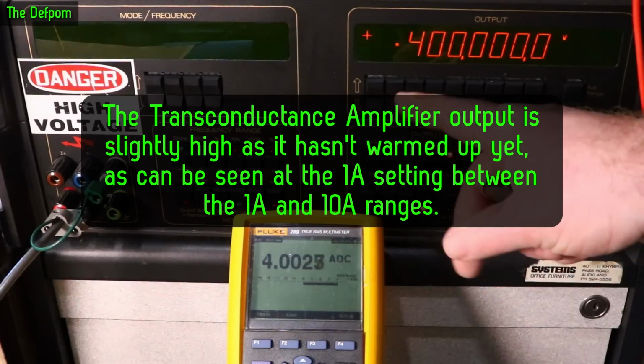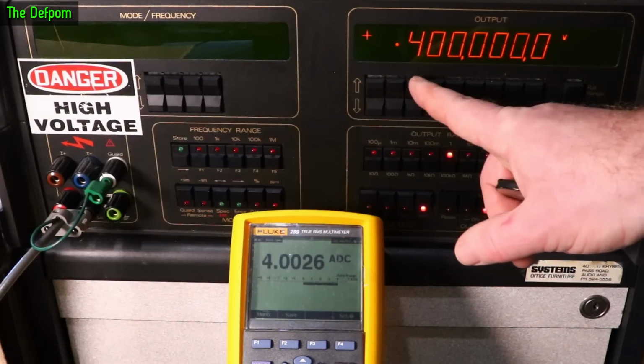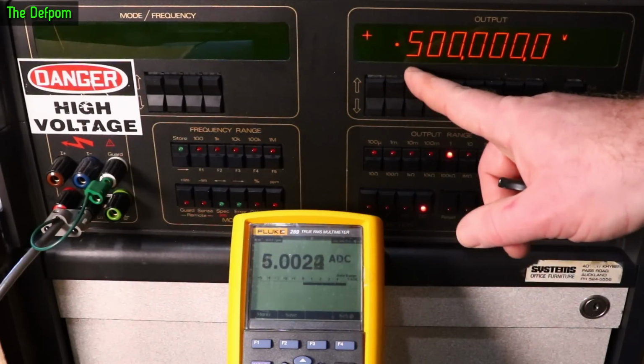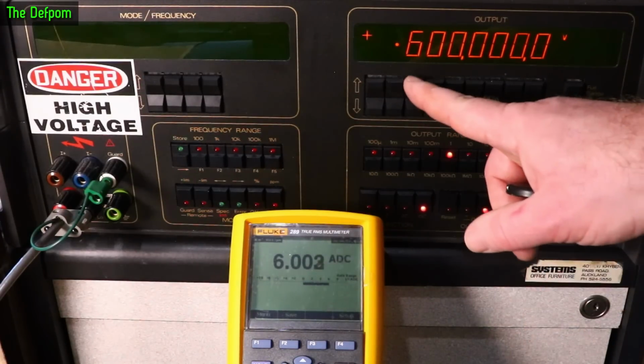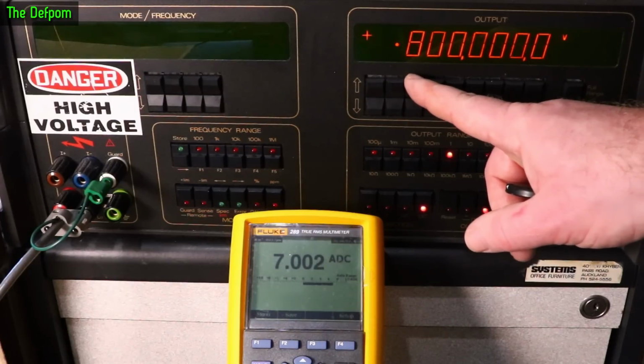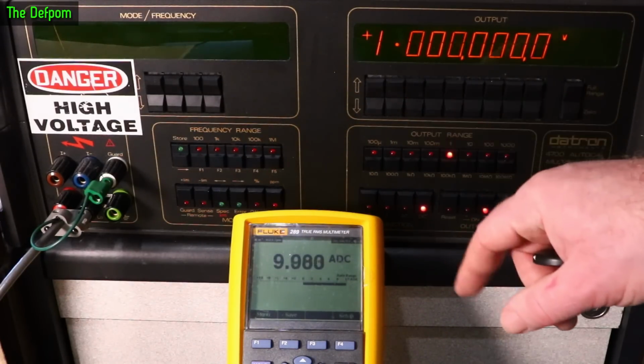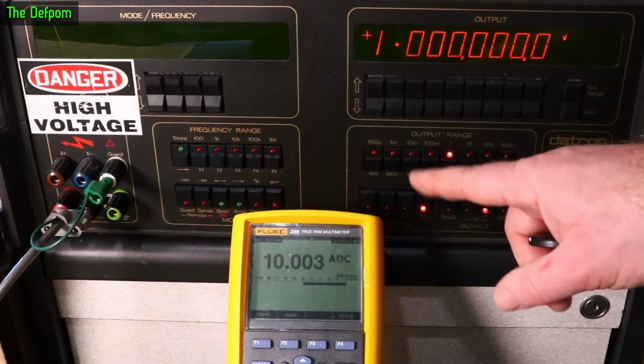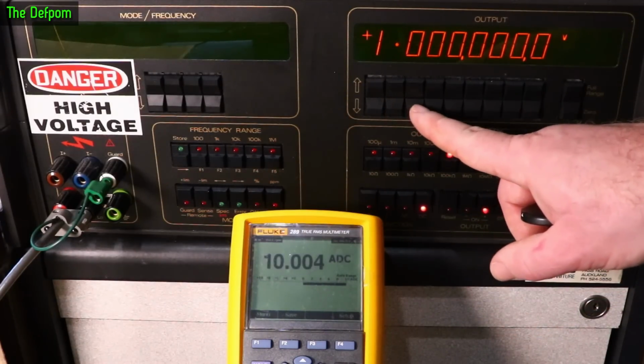Now my transconductance amplifier is not warmed up yet. It should warm up for about an hour or so really, and I've only had it on for a few minutes, so it's not going to be perfect. But let's just give you an indication of rough accuracy. It's within a few counts, isn't it? A couple of counts there. Yep. 10 amps flashing to say it's maximum range.